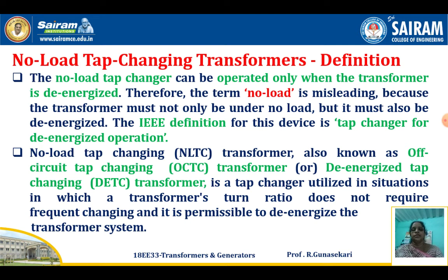The no load tap changing transformer, the abbreviation is NLTC, is also known as off load tap changing or off circuit tap changing transformer, the abbreviation is OCTC, or de-energized tap changing transformer, abbreviation DETC. Generally, a no load tap changer is utilized in situations in which the transformer's turns ratio, that is K, does not require frequent changing, and it is permissible to de-energize the transformer system.